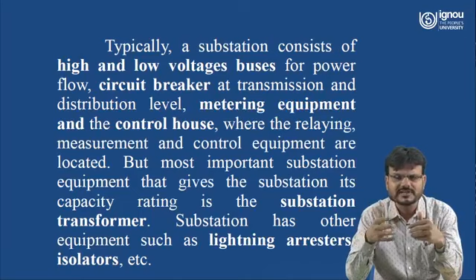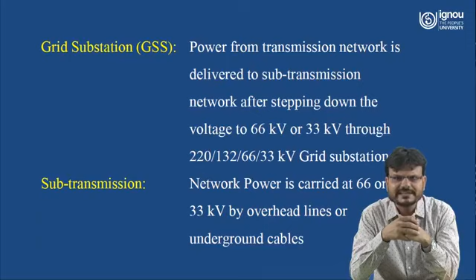Now there are different terminologies that we have to understand. What is a grid substation? A grid substation means power from the transmission network is delivered to the sub-transmission network after stepping down the voltage to 66 kV or 33 kV through a 220, 132, 66 or 33 kV grid substation. The second term is sub-transmission network, where power is carried at 66 or 33 kV by overhead line or underground cables.